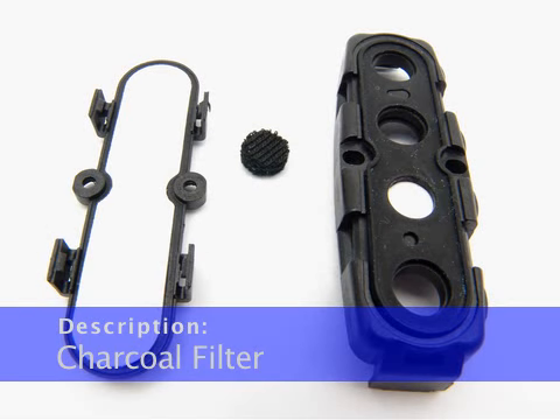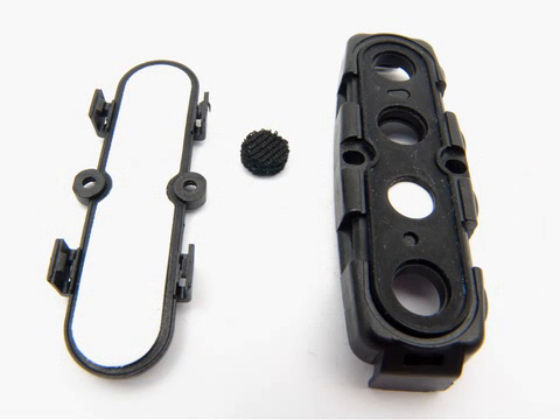The charcoal filter disc is located in the CO sensor port of the sensor retainer. It is black, has a woven texture, and is impregnated with a hydrogen sulfide absorbing material. It fits into a recessed area of that port. The CO sensor will respond if exposed to hydrogen sulfide and certain hydrocarbon gases. The charcoal filter scrubs these gases out of the gas sampled to avoid false CO readings. The H2S absorbing material added to the charcoal filter extends its H2S absorbing life. If false CO readings are noticed, especially high readings in the presence of H2S, change the charcoal filter disc.